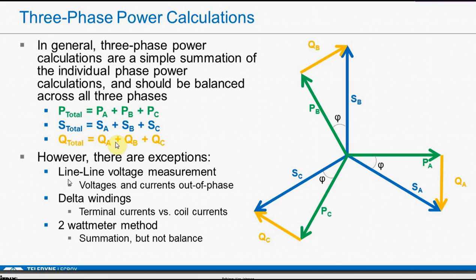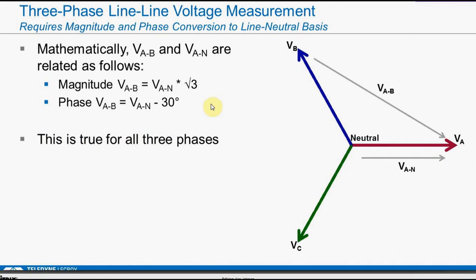There are some exceptions, right? If I'm making a line-to-line voltage measurement, I have a voltage and a current that are out of phase. They don't relate to each other directly, so we have to do something about that. Another thing you have to think about is a delta winding. You've got a terminal current versus a coil current. Also, for a lot of really good reasons, sometimes a customer might use a 2-wattmeter method. The 2-wattmeter method allows you to use only 4 signals to make the measurement instead of 6, which is useful when you might have a portable instrument or you want a limited number of inputs and you need to economize on the number that you use for your power measurements. It's a very valid method. We're going to cover what you do with the exceptions. The general case is very straightforward. The exceptions take some explanation.